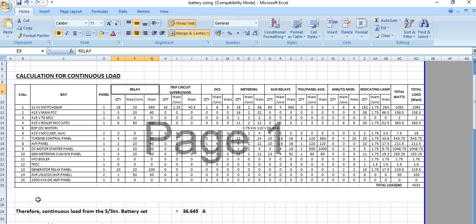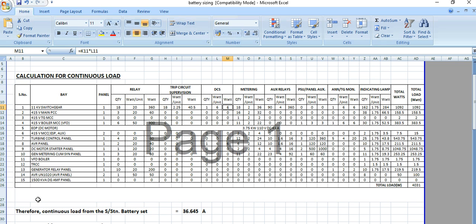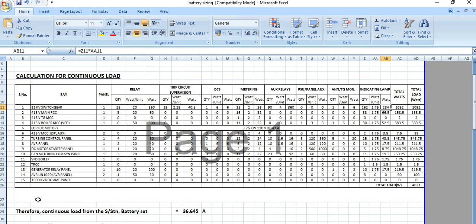For the relay requirement, there are 18 relays for the 11kV switchboard. Power per relay is 20 watts, so total is 18 × 20 = 360 watts. For trip circuit supervision, 18 numbers at 2.25 watts per unit gives a further total. Additionally, there are DCS power supply requirements, metering, auxiliary voltage, and indicating lamps — all contributing to the total DC power requirement.